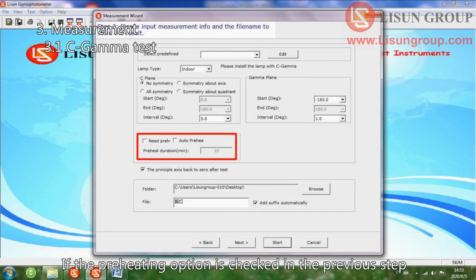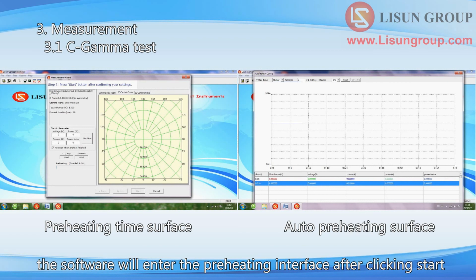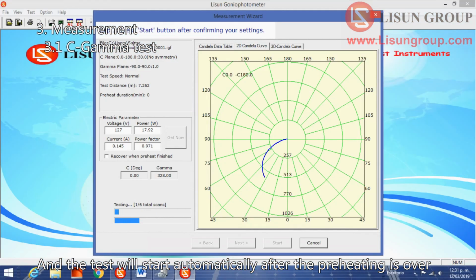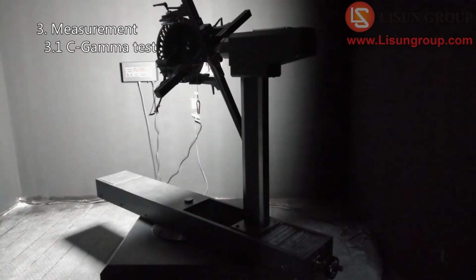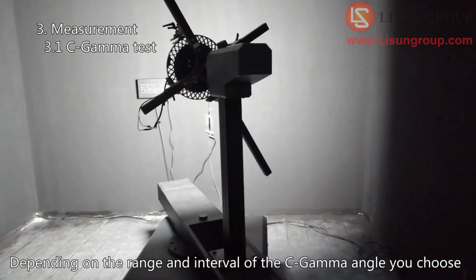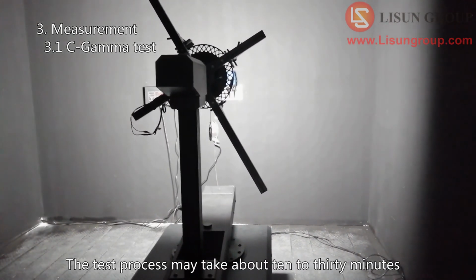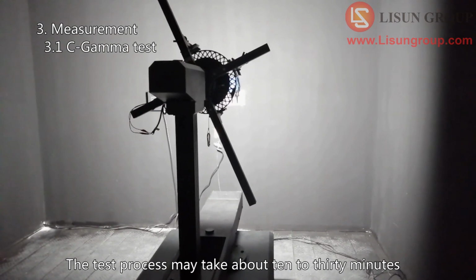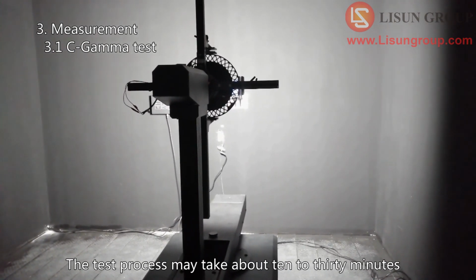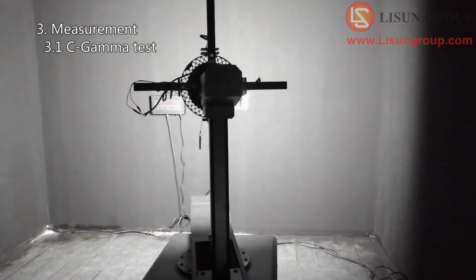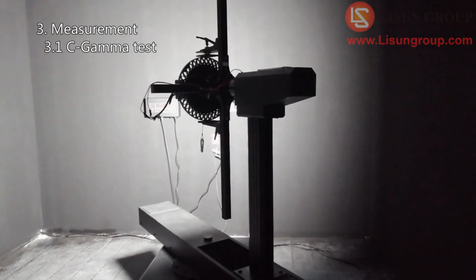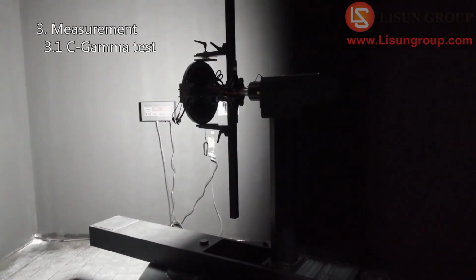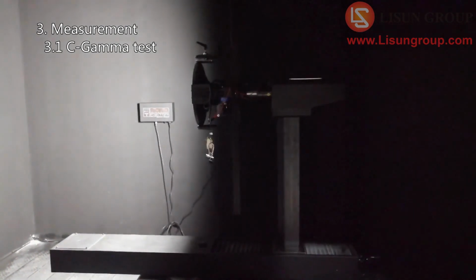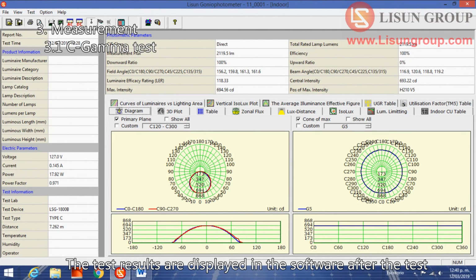If the preheating option is checked in the previous step, the software will enter the preheating interface after clicking Start. And the test will start automatically after the preheating is over. Depending on the range and interval of the C-gamma angle you choose, the test process may take about 10 to 30 minutes. The test results are displayed in the software after the test.